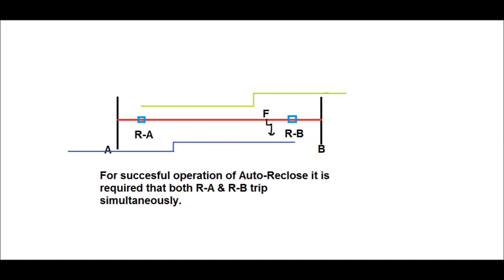Now, a fault occurs in zone 2 from the relay at the A end and zone 1 at the relay at the B end. Relay B will trip at zone 1 time, that is instantaneously, but the relay at the A end trips at zone 2 time. Therefore, for successful operation of autoreclose, relay A and relay B must trip simultaneously. That should be possible with a carrier aided protection trip.